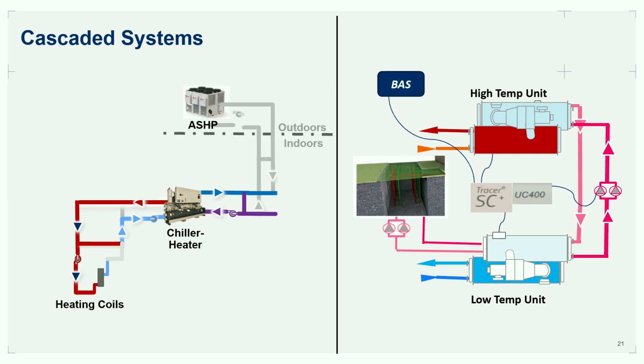We're going to be talking about COPs of 3 and 4 at 0. You can't typically get that with your traditional air-to-water heat pump. So then what you're doing with that 50 to 60 degree water, you're putting that into an evaporator of another chiller heater, and then doing another standard set of lift to get to your desired leaving water temperature.